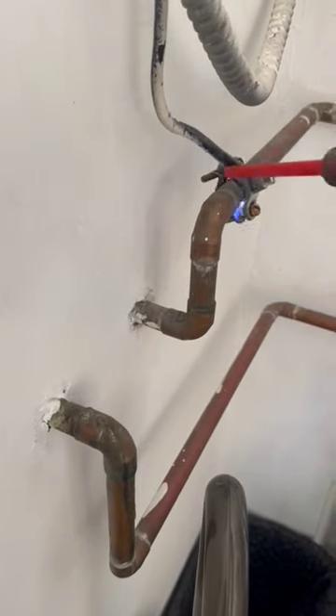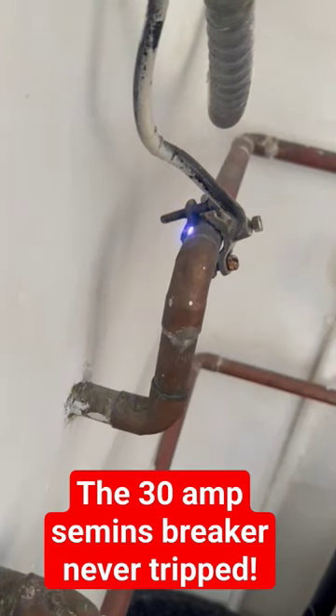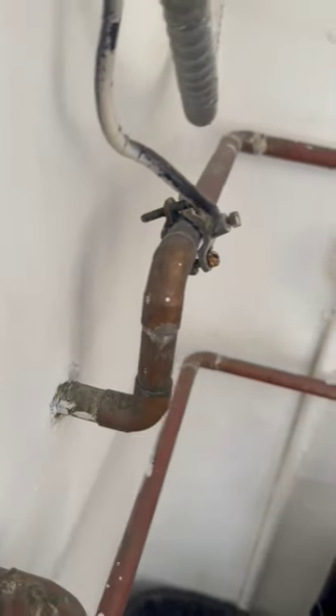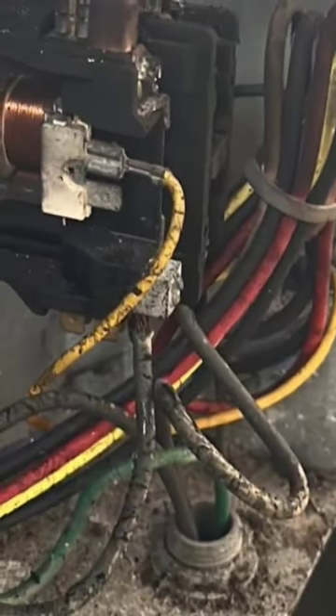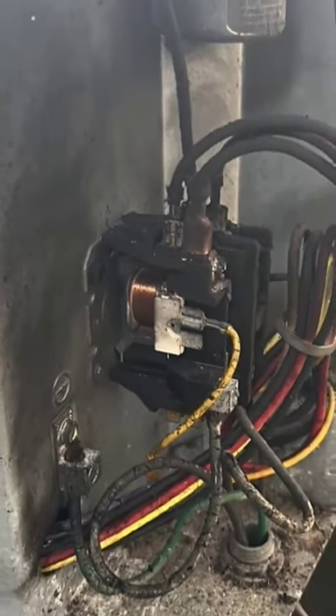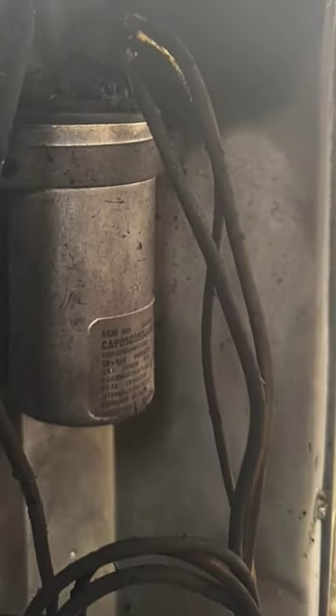Get a load of this cold water bond welding. Looks like the house was struck by lightning and it damaged an AC unit. The funny thing is, the grounding for the whole house was not bonded to the meter main combo panel — that cold water bond was acting as the whole house ground, but the clamp was loose.